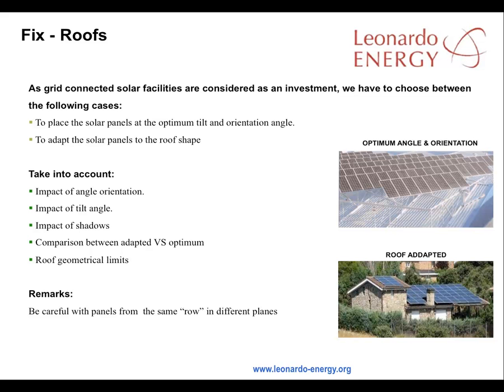With rooftop facilities, a choice has to be made between following the shape of the roof or tilting and orienting the panels to optimize their performance. The option that delivers the greatest investment return should be chosen. The variables to be taken into account are the impact of the angles of orientation and tilt, any shadowing, a comparison between the expected energy output from the two options, and the roof's geometrical limits. Care has to be taken when calculating the performance of panels that are on the same row, where variations in the roof levels would mean that the panels are actually on different planes.